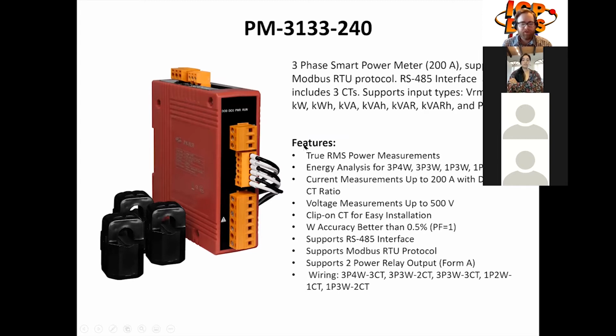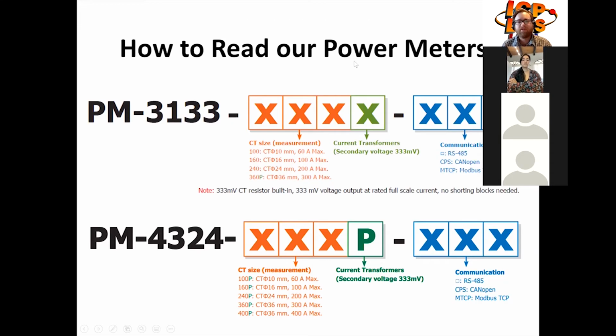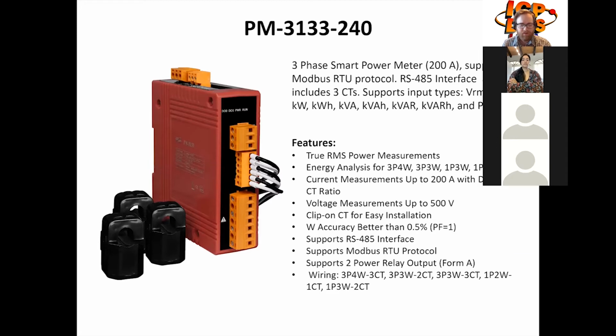The first power meter we're looking at is the PM-3133-240. From the 240, you can tell that it's the 24 millimeter CT with the 200 amps maximum. This is a smart power meter designed to give you access to real-time electric usage for one 3-phase circuit. It's a high accuracy module. It can be applied on both the low voltage primary side or medium and high voltage secondary side. It enables users to obtain reliable and accurate energy consumption readings from your monitored equipment in real time.